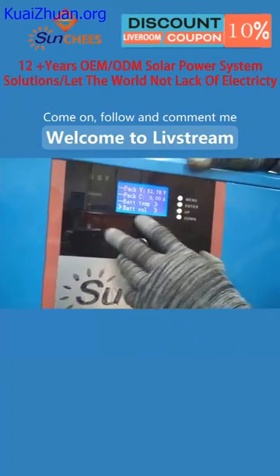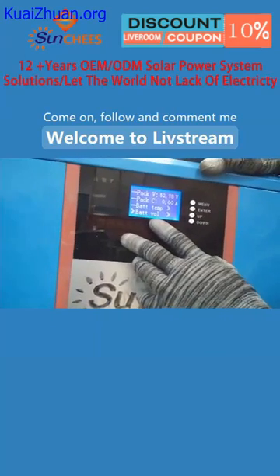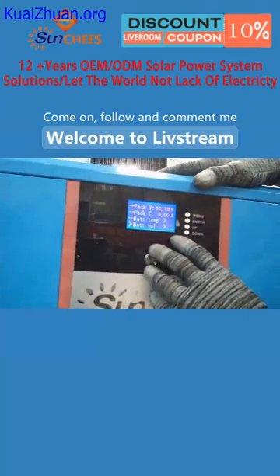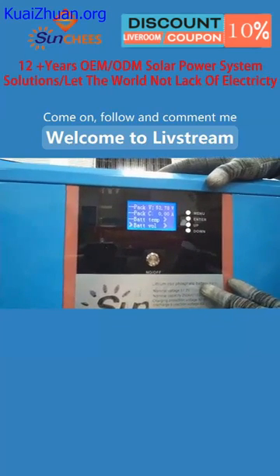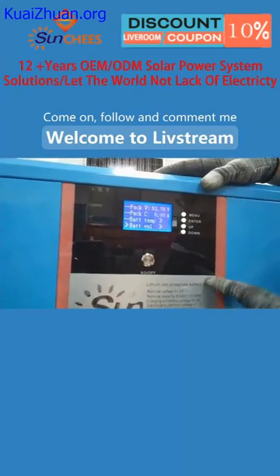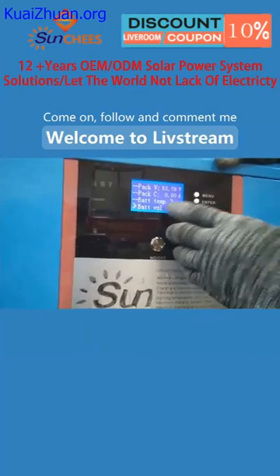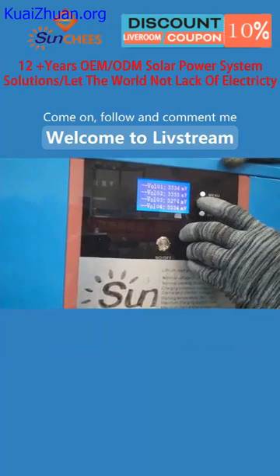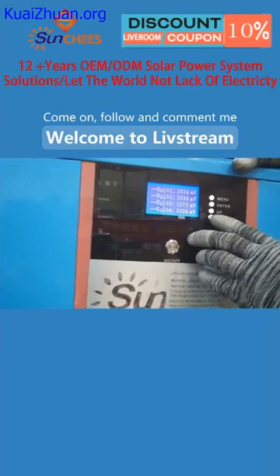And on the fourth line, you can see the battery voltage for each lithium battery cell. For the 51.2 volt lithium battery, we use 16 pieces of lithium battery cells connected in series. So you just get inside, you will see the voltage of the 16 battery cells.